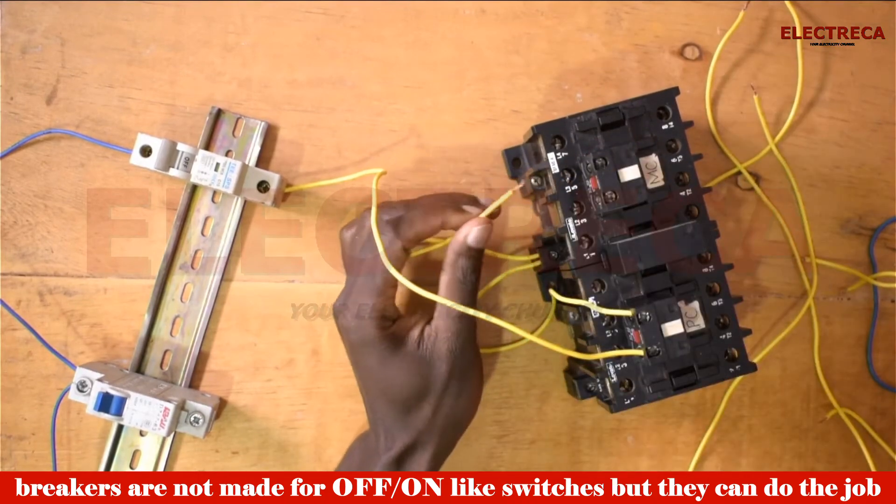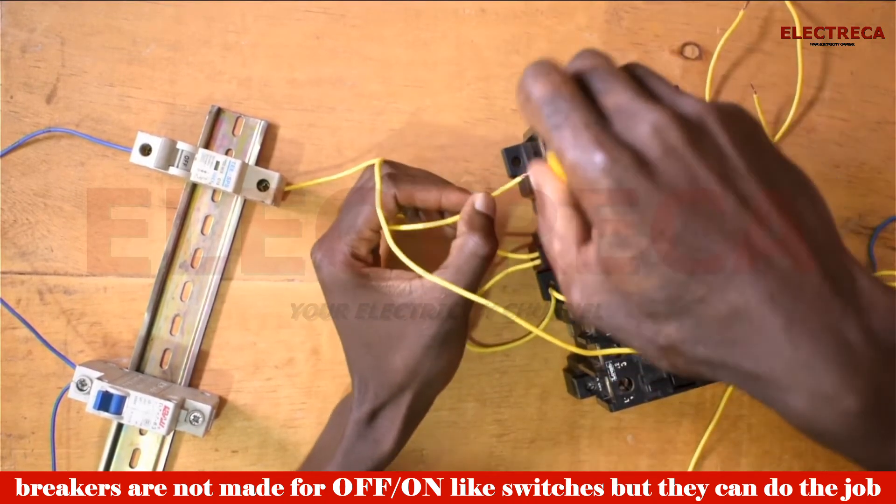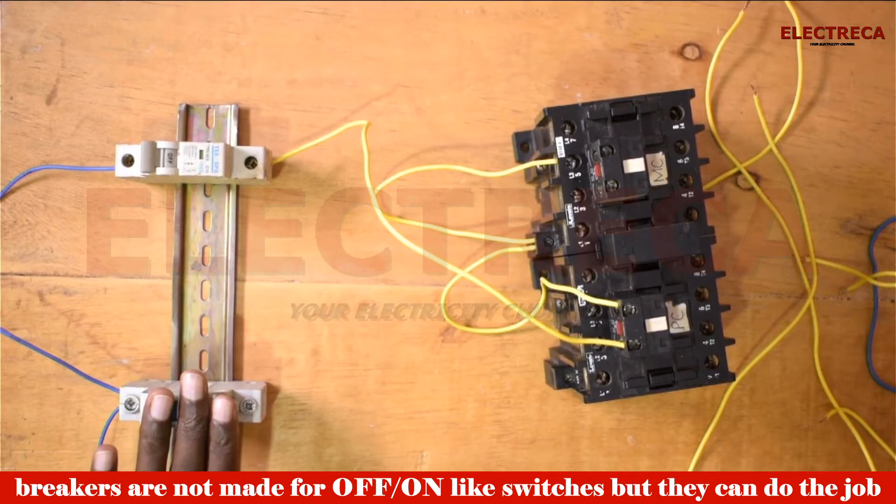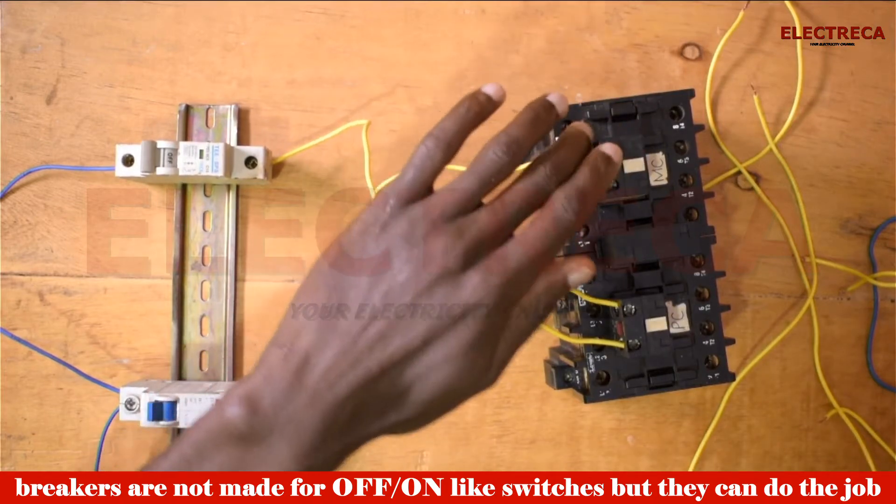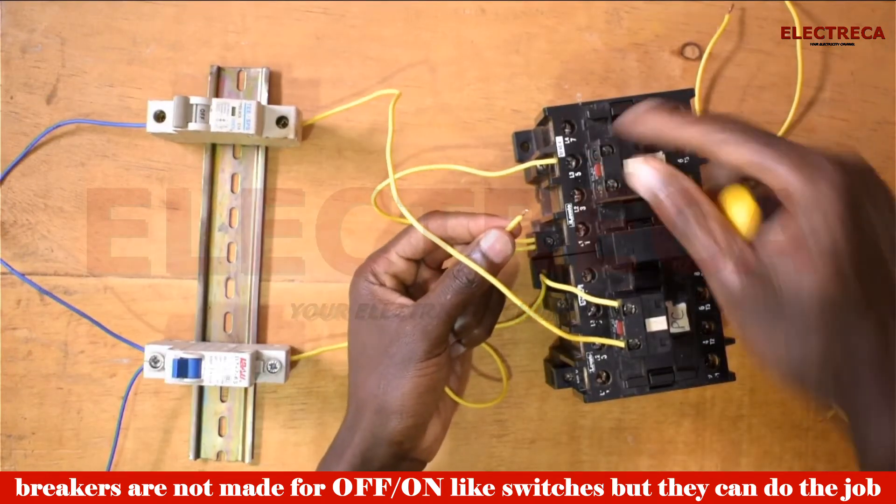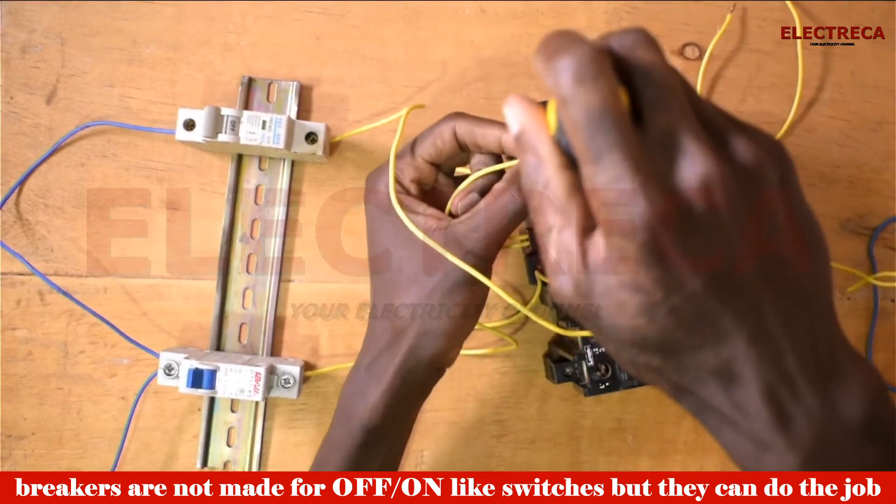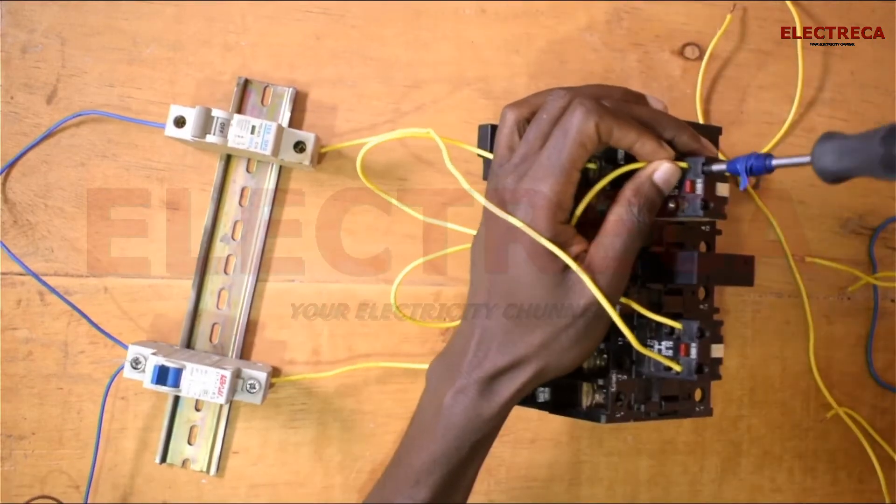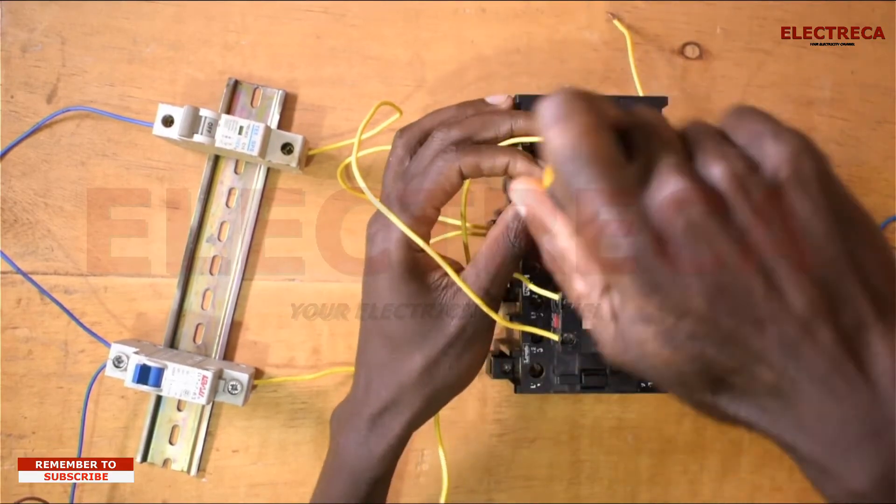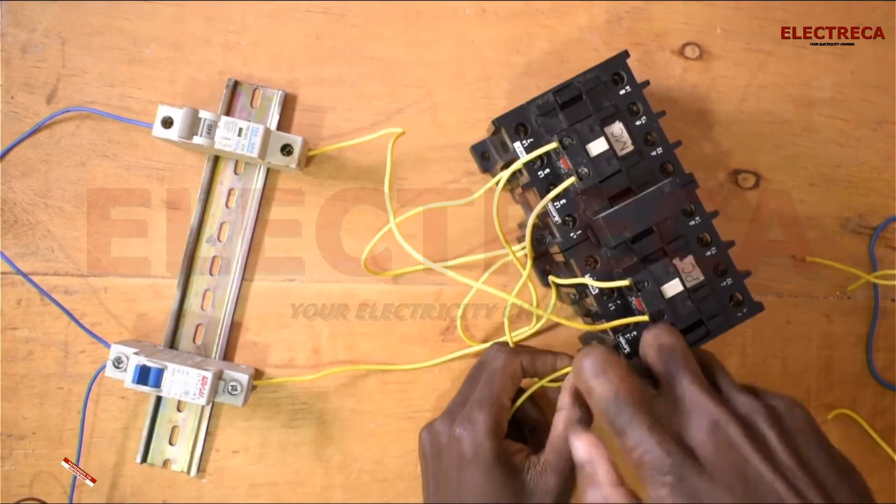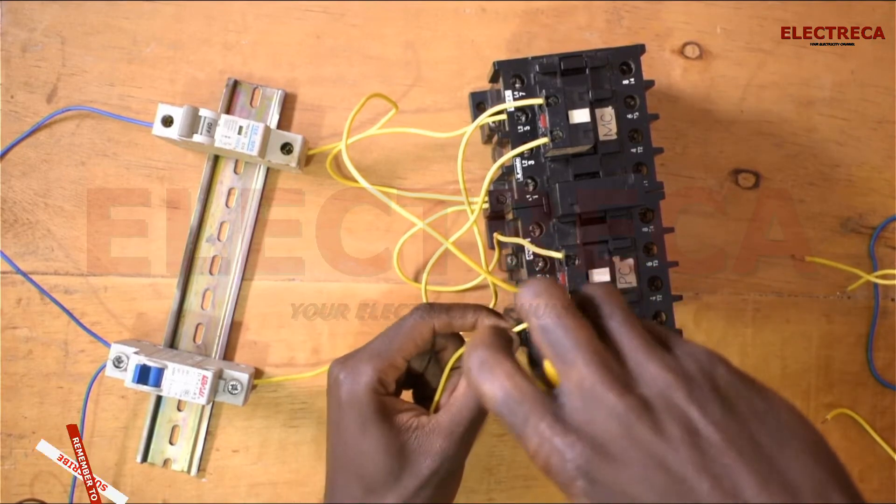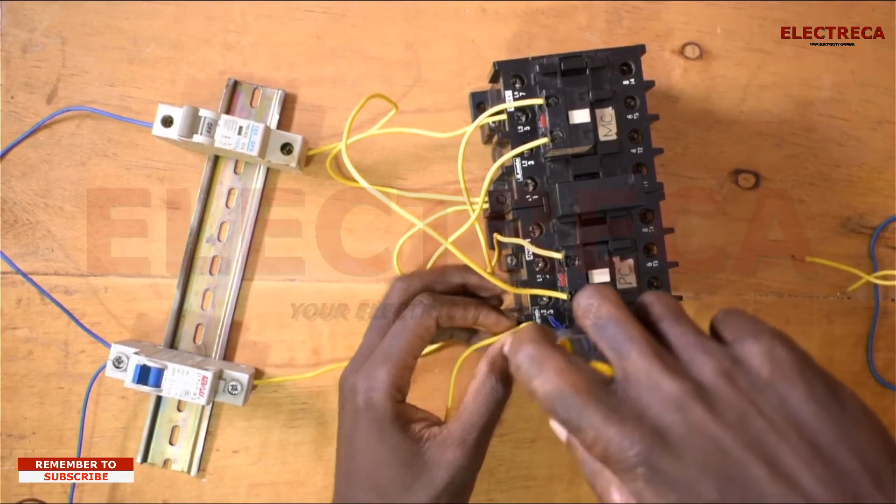And we will have to supply one of the contacts for our light. Same thing with the generator control breaker. It also goes through the normally closed of the main contactor. This will now go to the coil, and this one to supply our light that we want to connect.